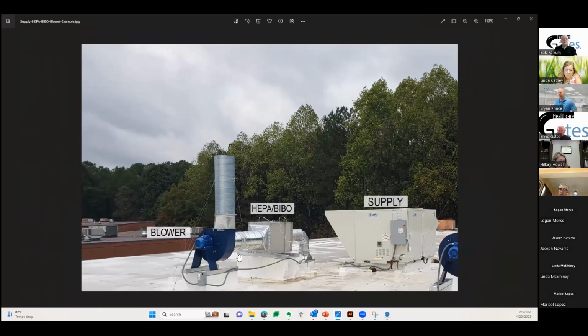One thing I want to talk about is filtration. In an earlier draft, maybe around 2014-2015, of USP 800, it said exhausted air must be HEPA filtered. That piece actually came out of the final 2019 document. I don't know why, I guess they assumed everyone in a powder handling situation would be attaching their powder hoods, so in theory all the HEPA filters in the hoods are picking up the particulates. Great.